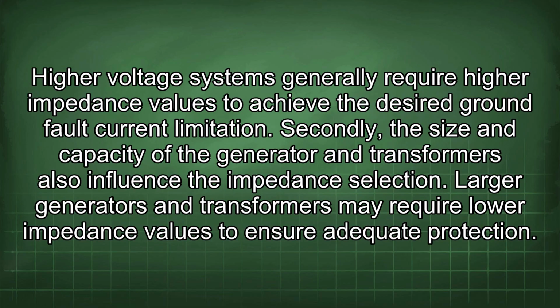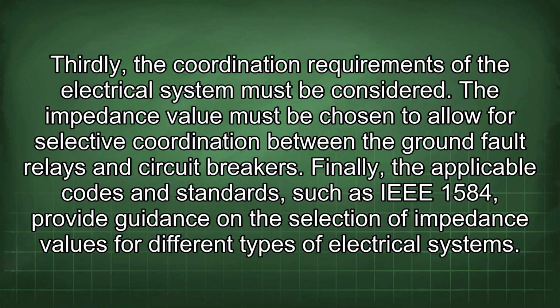Higher voltage systems generally require higher impedance values to achieve the desired ground fault current limitation. Secondly, the size and capacity of the generator and transformers also influence the impedance selection. Larger generators and transformers may require lower impedance values to ensure adequate protection. Thirdly, the coordination requirements of the electrical system must be considered. The impedance value must be chosen to allow for selective coordination between the ground fault relays and circuit breakers.